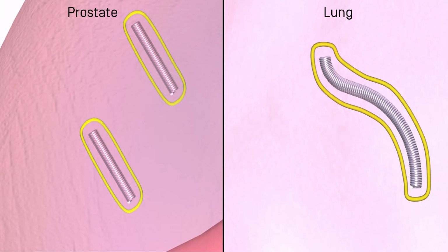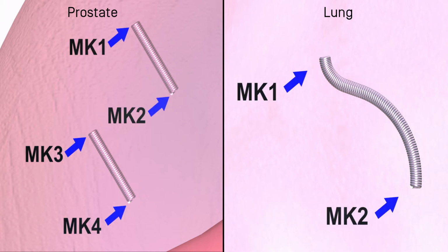Most treatment equipment allows for the marker to be contoured for tissue location and position. Another method is to use the endpoints, or points along the marker, for reference and localization. VisicoilMR's linear design offers more location information from only 2 needles, compared to typical solid gold markers requiring a minimum of 3 needles, often larger in size.